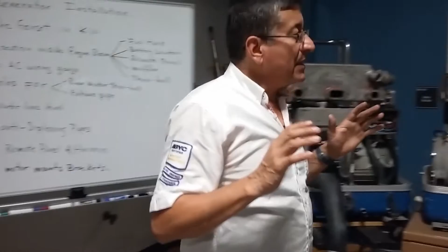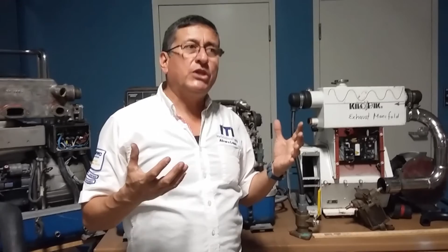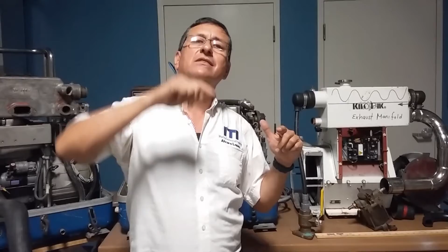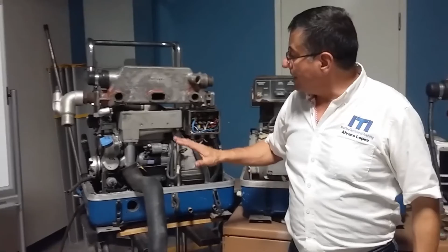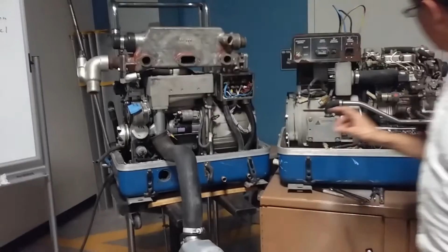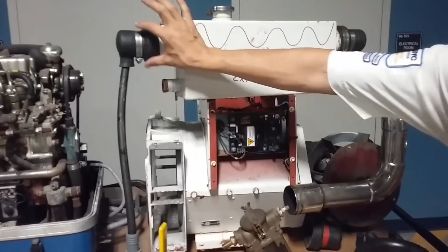What is the mark that you use for reference when you try to take the decision if the generator needs anti-siphon or not? Normally, the secret is this: check the exhaust manifold and verify where. This is the exhaust manifold. This is the heat exchanger. Look, that's the through hole.